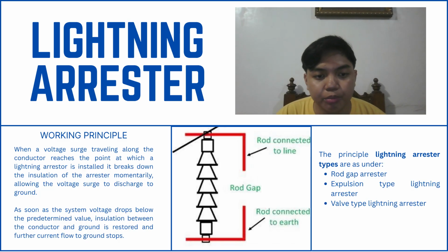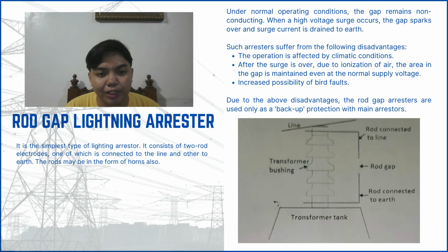So, what's the working principle of a lightning arrestor? When a voltage surge traveling on the conductor reaches the point at which a lightning arrestor is installed, it breaks down the insulation of the arrestor momentarily, allowing the voltage surge to discharge to ground. As soon as the system voltage drops below the predetermined value, insulation between the conductor and ground is restored and further current flow to ground stops. The principal lightning arrestor types are as under. The first one is the rod gap arrestor, second is the expulsion type lightning arrestor, and lastly is the valve type lightning arrestor. So what is a rod gap lightning arrestor?